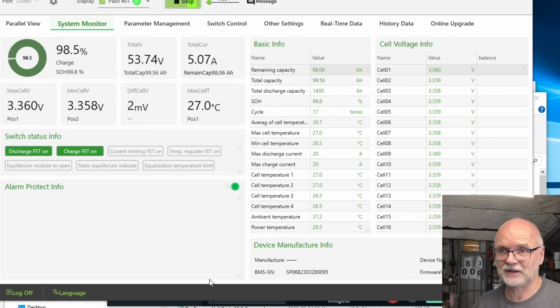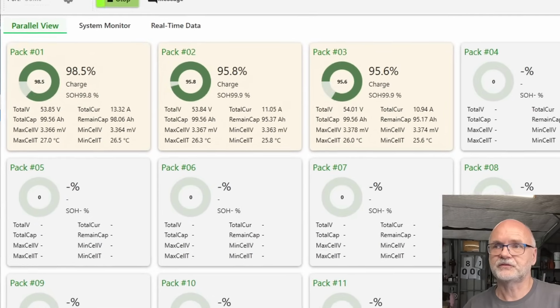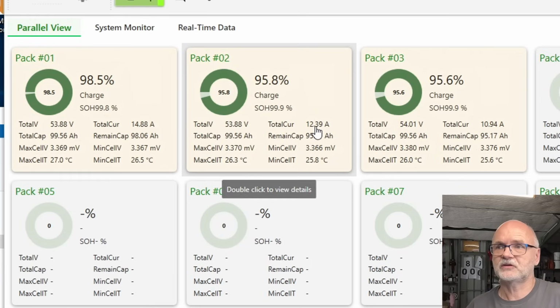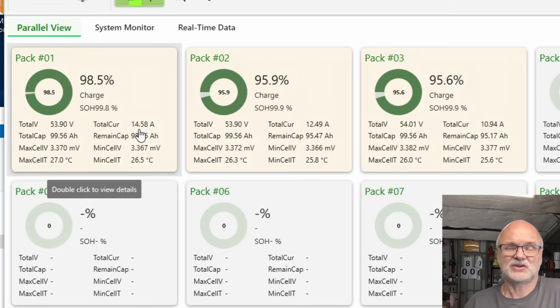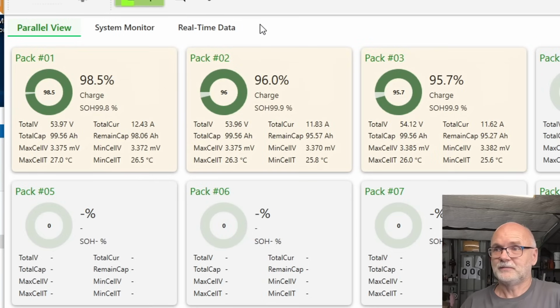Let's have a look at the other cells. I reconnect them back, then we can see them all at once. And we should see them coming up. Yeah, see, they are still charging, 12 amps, 10 amps. See, we are still charging with 14 amps continuously, and 98.5%. And it is the same at the bottom when you discharge this battery. At some point it shows like 4% or something, and it keeps discharging and discharging. Even at 3.1 volts or something, it shows you 4%. So the state of charge estimation is still not fixed, I would say, from what I can see right now. But let's give it a couple more minutes here, and then we will see if there's any improvement, but I don't think it is at the moment.